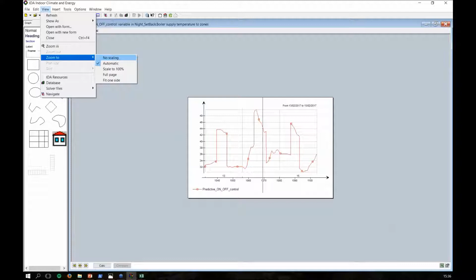When you have an on-off controller, it cuts way, way earlier. Let's see where that cuts. Now remember, the on-off controller doesn't have a schedule, so it's determining when to start and when to turn off. And we can see here that on one of the days, it starts to ramp up at 7:30. On the next day, it starts to ramp up at 7:21. On the third day, it starts to ramp up at 7:23.